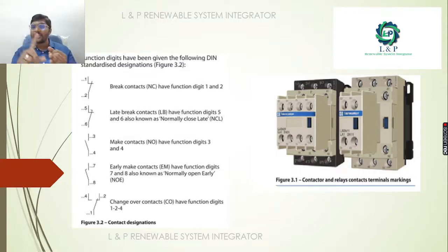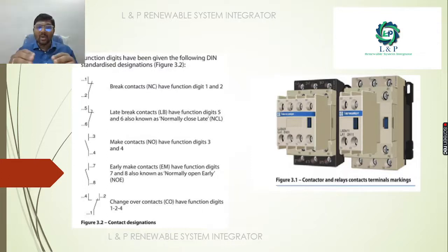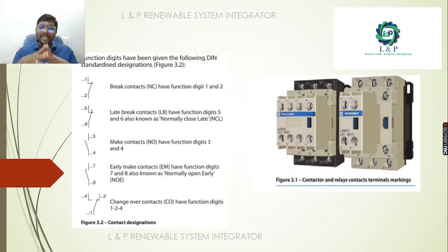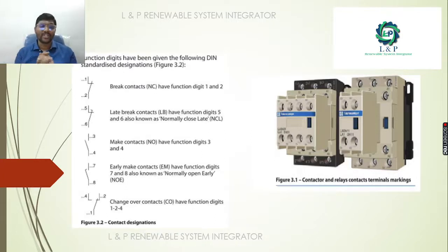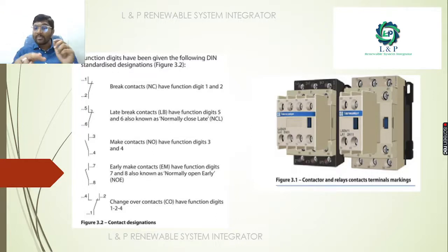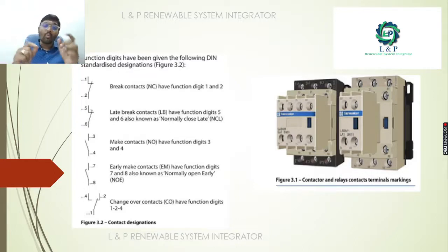If the contact is making (normally open), the function digit will be 3 and 4. For an early make contact (normally open early), the function digit will be 7 and 8. For a changeover contact, the function digit will be 1, 2, and 4.